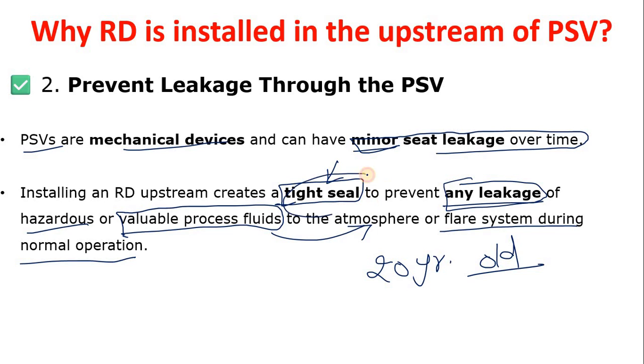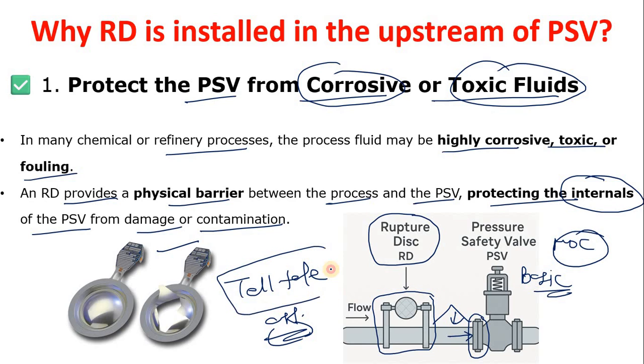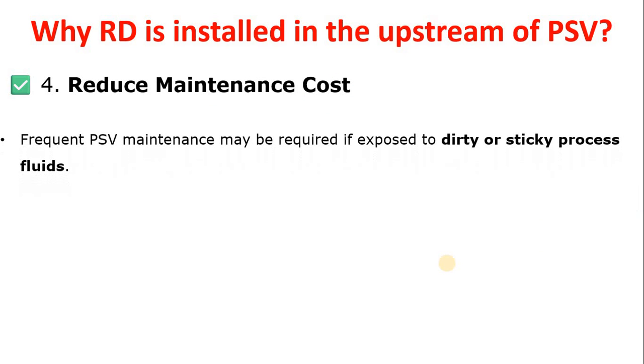You might ask: if an RD is installed and it bursts, how will you know? There is an arrangement called a tattle-tail assembly. If the RD bursts or starts leaking, the tattle-tail assembly will alert you so you know the RD has operated and your PSV internals are now in contact with the process fluid. You can then attend to and replace the RD.